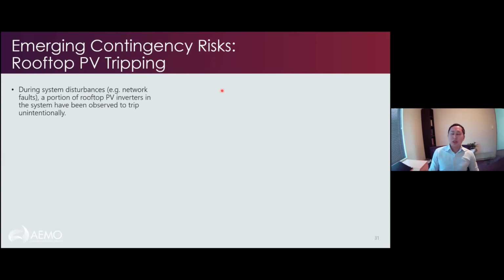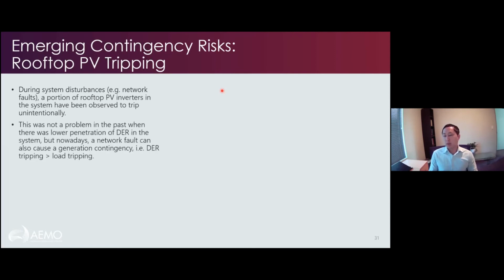The next issue we're seeing is of emerging contingency risks, and this is one of rooftop PV tripping. So what we're seeing is that during system disturbances, so really network faults, short circuits on transmission lines, they are causing voltage deviations or disturbances throughout the transmission system and then down into the distribution system. And we're seeing that a portion of rooftop PV inverters are just tripping off unintentionally. And this wasn't a problem back in 2011, 12, 13, and in the past because there was low DER penetration. But nowadays we're getting to a point where a network fault can also cause a generation contingency.